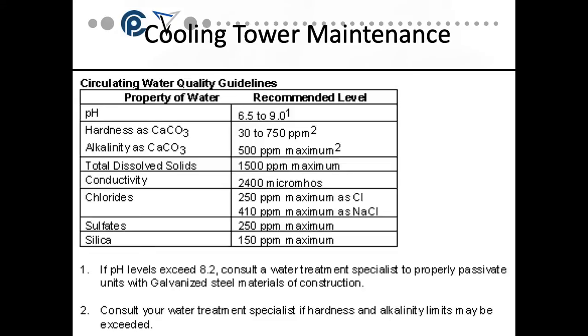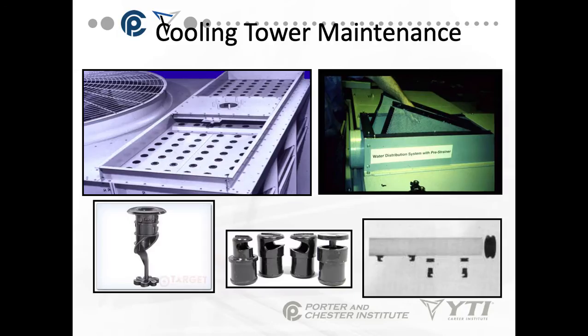Okay, you will also get guidelines on what the circulating water quality needs to be. For example, the pH of the water needs to be 6.5 to 9.0. Hardness, alkalinity, dissolved solids, conductivity. All of this will be given to you with the maintenance requirements and with the technical specification of the tower. Now, most companies out there do contract out their water maintenance and the water quality in a cooling tower system to a specialty contractor. Normally, this is not something that's done in-house because of the testing that needs to be done. But every company handles that differently, and you as a technician may be trained to do that proper testing.